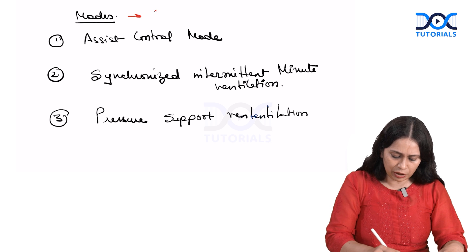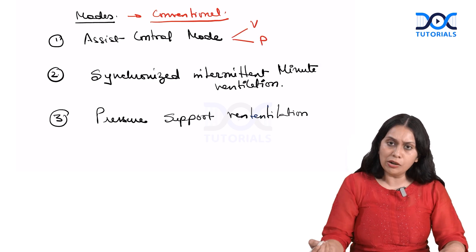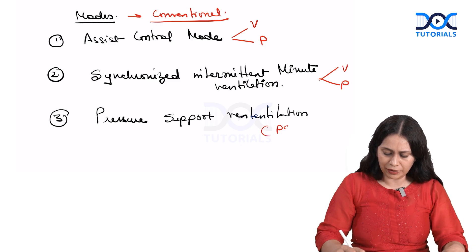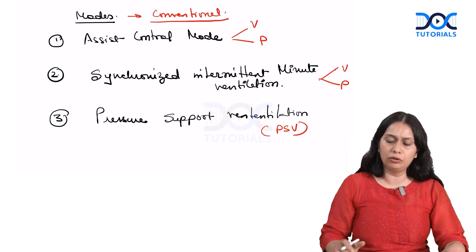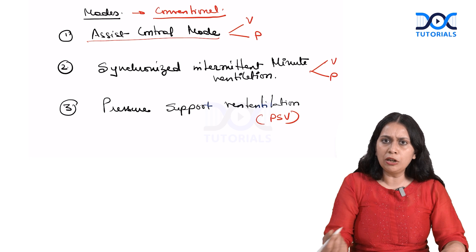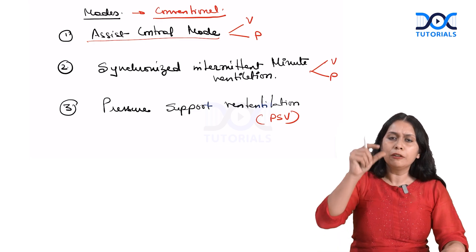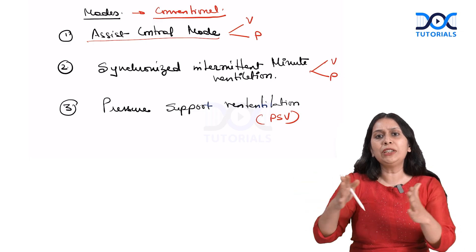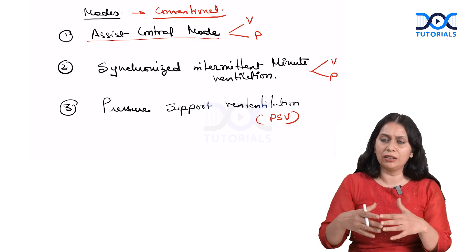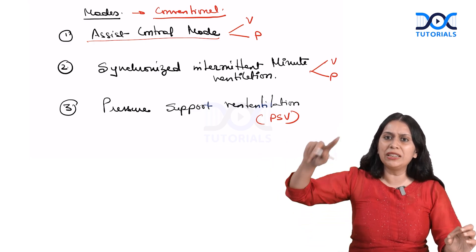The conventional modes include assist control mode — which has both volume and pressure control options — synchronized intermittent mandatory ventilation (SIMV), also with volume and pressure control options, and pressure support ventilation (PSV), which is a spontaneous mode. In assist control mode, each and every breath is either controlled or assisted by the ventilator with a fixed tidal volume delivered. In SIMV, there are fixed breaths controlled or supported by the ventilator, and between two supported breaths the patient can breathe spontaneously — that breath is not fully controlled by the ventilator.